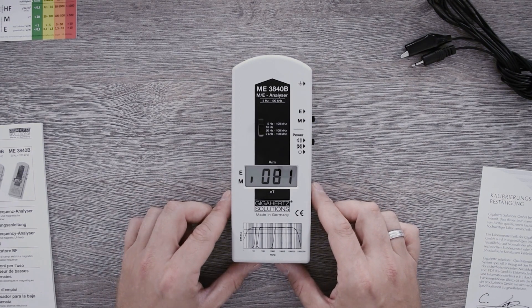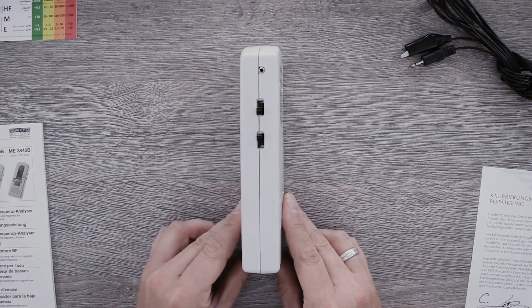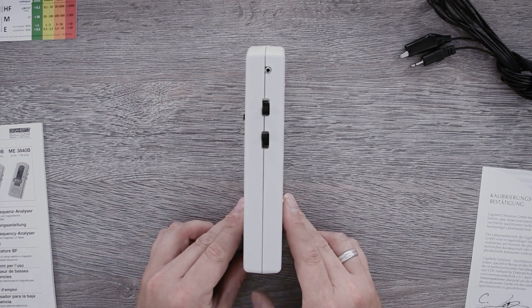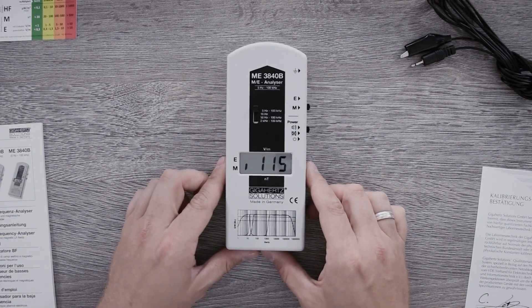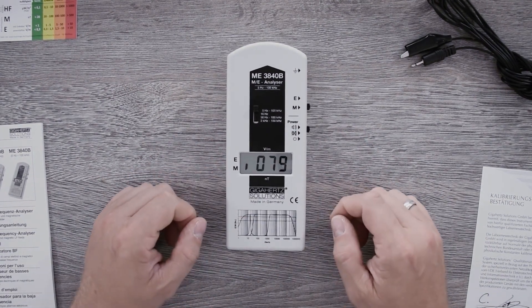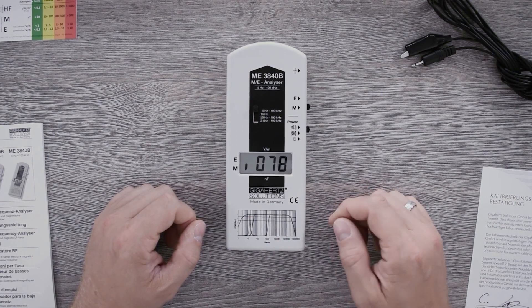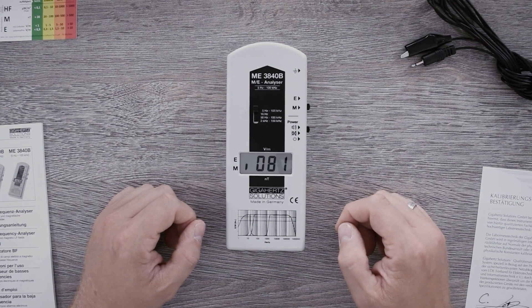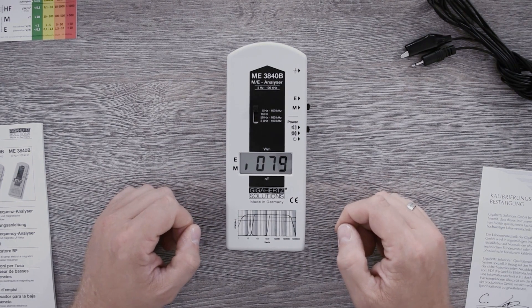This means you have to remember the measurement value in this position. We can turn the device and then also mark the measurement value here. Now turn the measuring device upright and also note the measuring value here. All three values are squared, added to each other and then the square root is taken. The result is then showing the three-dimensional radiation load which is affecting you at this very spot.